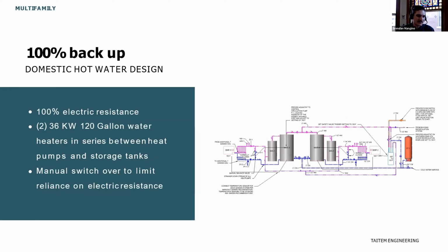The last is 100% backup. Like I said, this is new technology, and we wanted to add something just in case we needed to service the heat pumps prematurely or if something happened. So we do have 100% electric resistance backup. This is sized to be a 1-for-1 replacement. It's 2 36 kilowatt electric resistance elements in the 120-gallon water heaters. So these water heaters are piped in series.